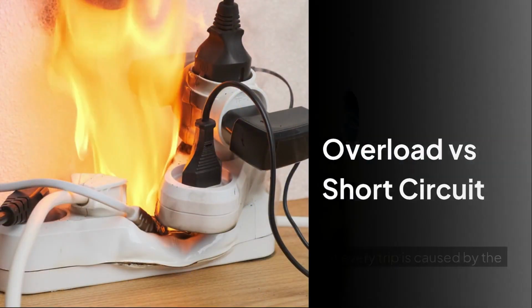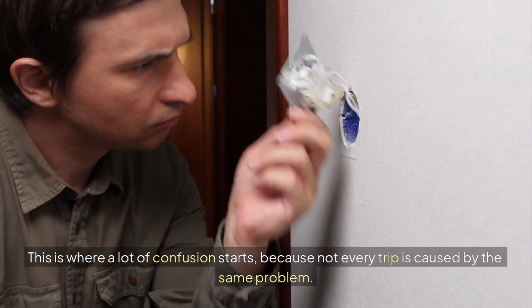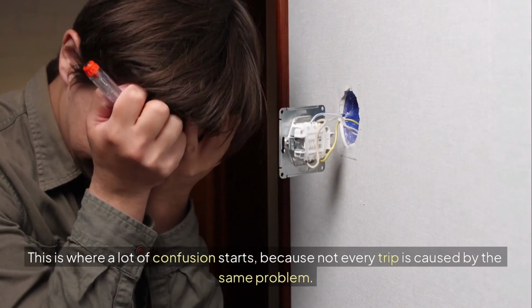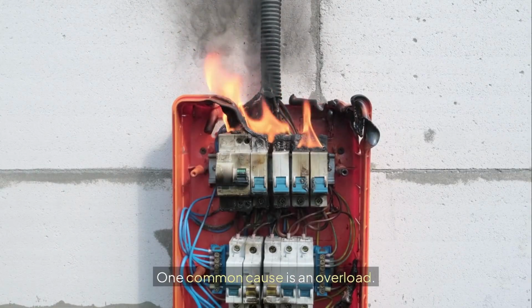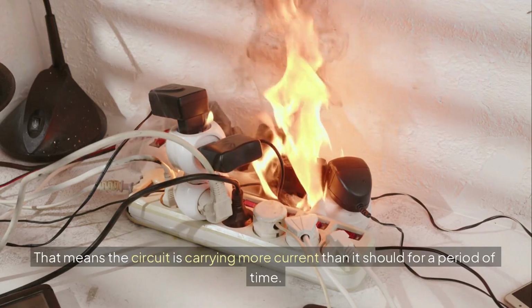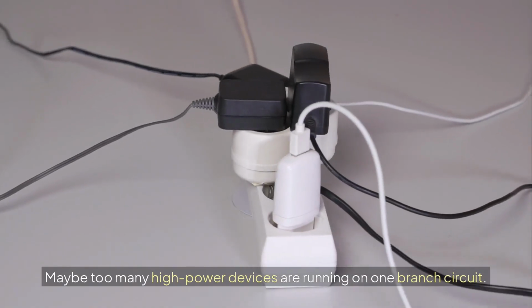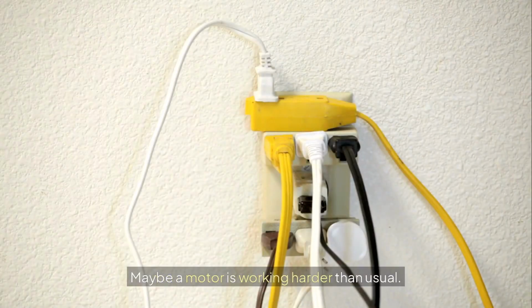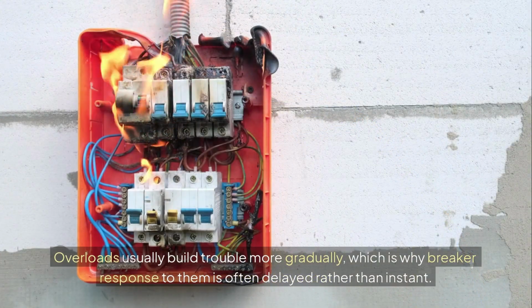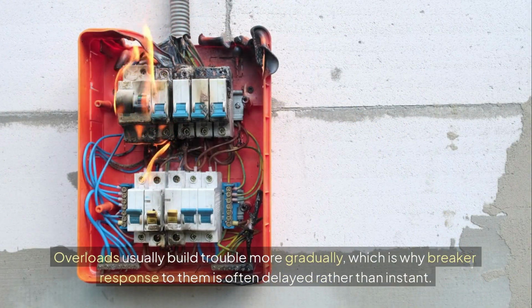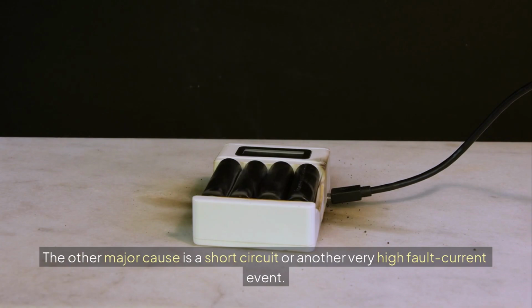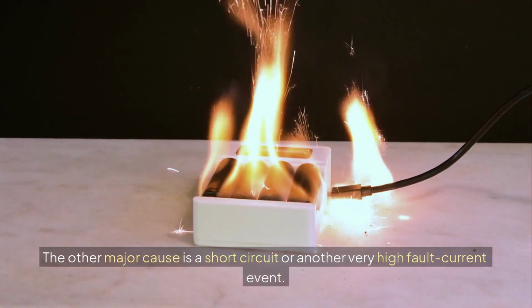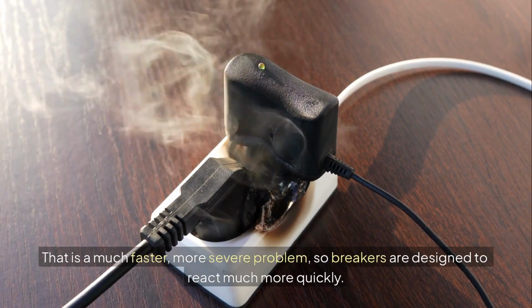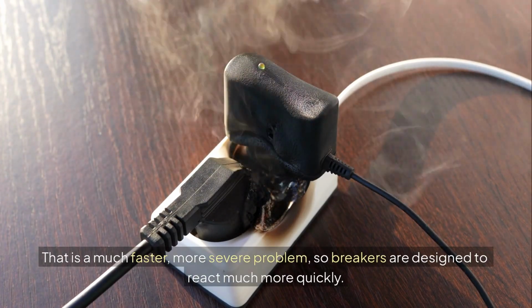Overload versus short circuit: this is where a lot of confusion starts, because not every trip is caused by the same problem. One common cause is an overload. That means the circuit is carrying more current than it should for a period of time. Maybe too many high-power devices are running on one branch circuit. Maybe a motor is working harder than usual. Overloads usually build trouble more gradually, which is why breaker response to them is often delayed rather than instant. The other major cause is a short circuit or another very high fault current event. That is a much faster, more severe problem, so breakers are designed to react much more quickly.